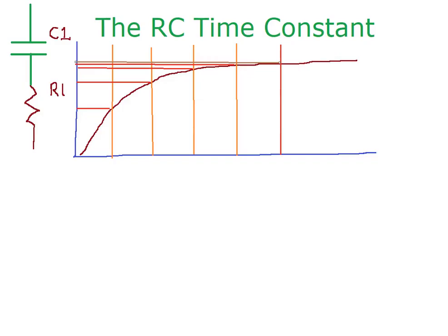So you have to look at the amount of residual resistance inside there. Now, the neon bulb will not conduct once it drops below the breakdown voltage, but it's still a good way of seeing it.